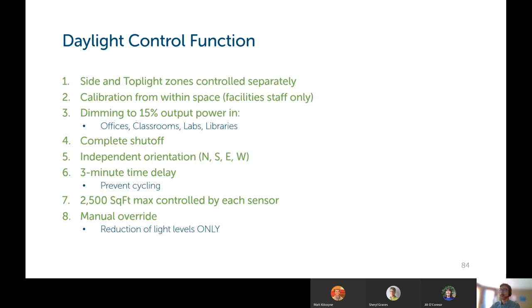Daylight control function: side and top light, so windows and skylights, need to be controlled separately. You need to be able to calibrate the daylight control functionality from within a space, just the facility staff, not the occupants. You have to be able to dim down to 15% total power output in offices, classrooms, labs, and libraries. You must be able to have complete shutoff of the lights when there's enough daylighting available. Each orientation of north, south, east, and west must have separate controls.